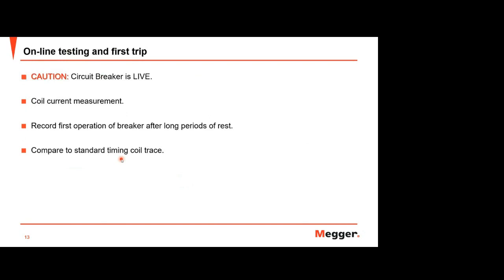Yeah, online testing and first trip, this has correlation, because we test first trip while the system is online. We need the system online. We need the circuit breaker to be live, and you also need coil current measurement and to record the first operation. This is the key. We need to record the first operation of the breaker after a long period of rest. This is the key point of first trip testing. We try to capture the first time the breaker trips after a long period of rest.